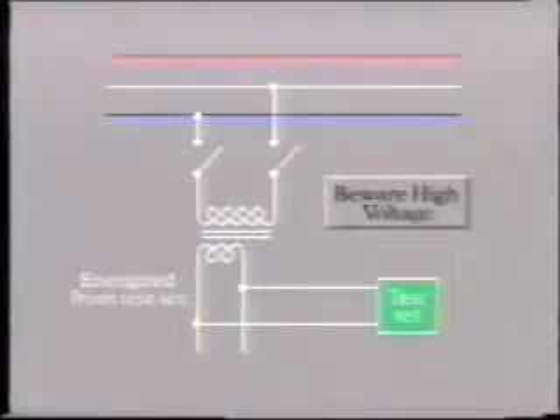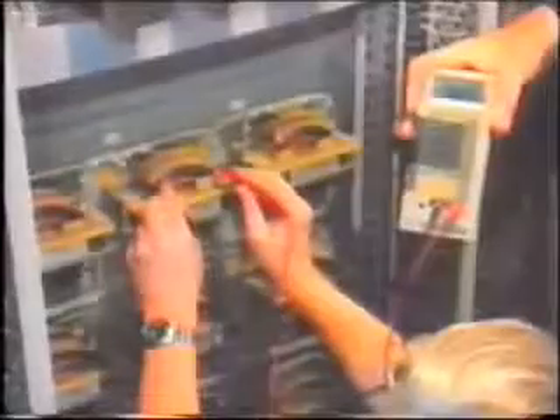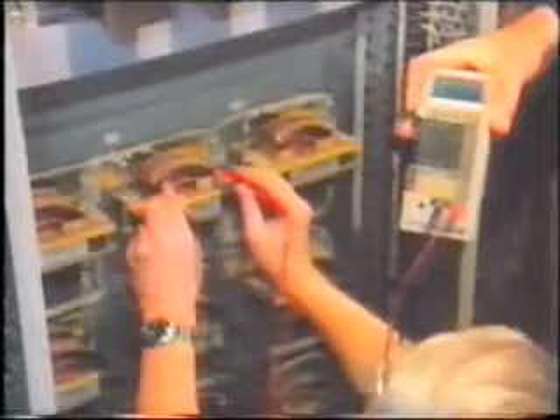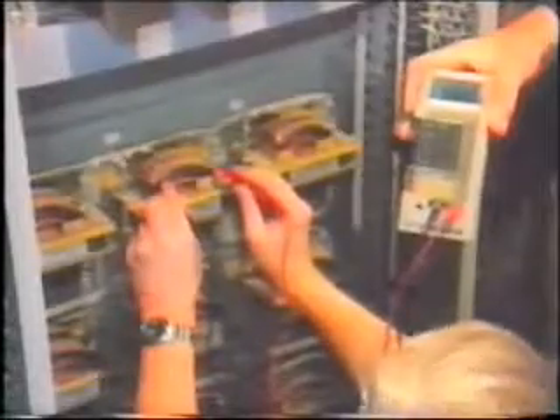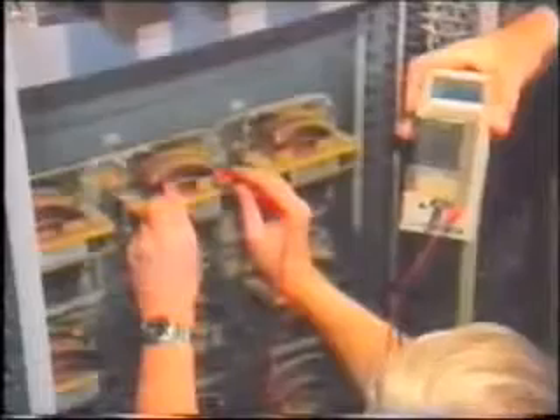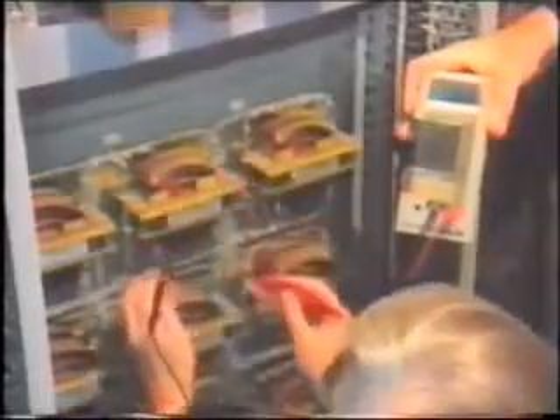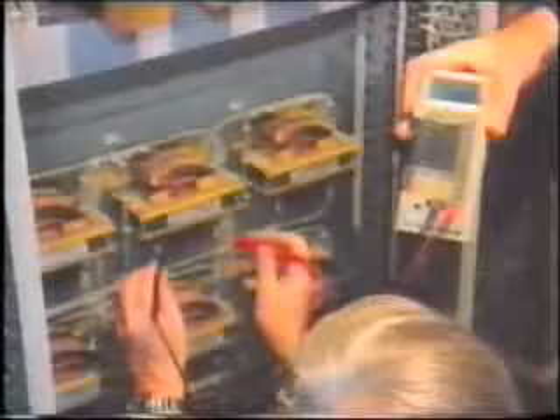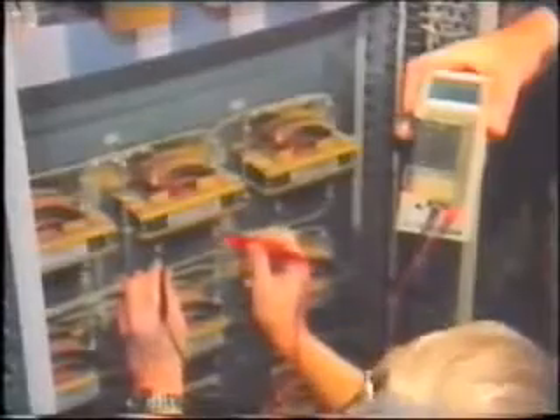Another potential hazard for relay technicians involves work around potential or voltage transformers, even when disconnected. For example, when the low voltage side is energized from the test equipment, the high voltage side will provide a very high voltage across its terminals. On other occasions, you may be performing troubleshooting tests on an energized VT or PT. In this case, remember never to short circuit the secondary winding. This can prove disastrous to you as well as to the transformer.